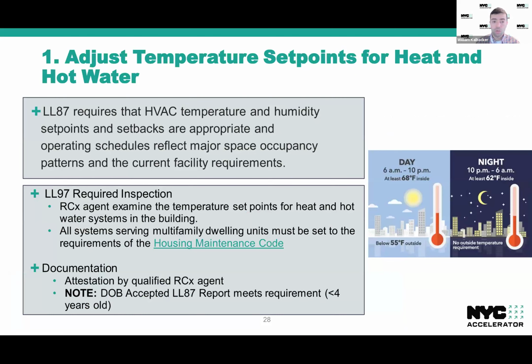The Local 87 requirement is specifically that HVAC temperature and humidity set points and setbacks are appropriate for the space and occupancy type. And specifically for Local Law 97 inspection requirements, the retro-commissioning agent has to examine the set points, make sure that they're all operating as expected and that they are compliant with housing maintenance code. There's a little graphic here to the right, which indicates basically you have to have a minimum inside temperature during daytime if it's cold out, and that temperature comes down a little bit during nighttime hours. In terms of the actual documentation requirements for this measure, you basically just need an attestation by the RCX agent. However, if the building has recently completed a Local Law 87 energy audit, that document can be submitted as proof of compliance as well.